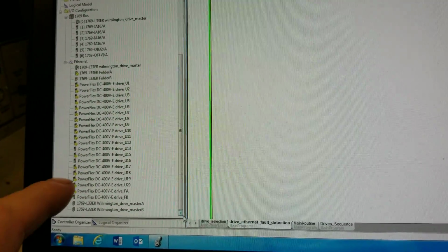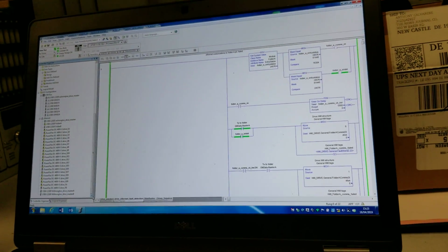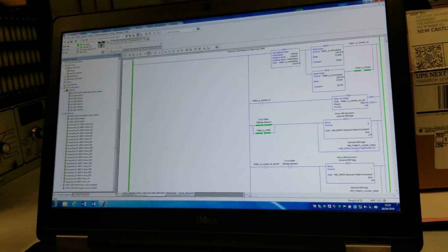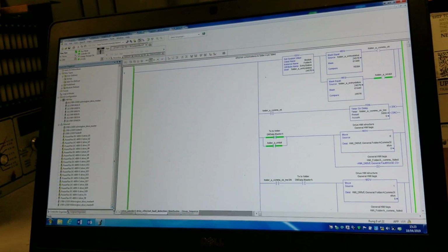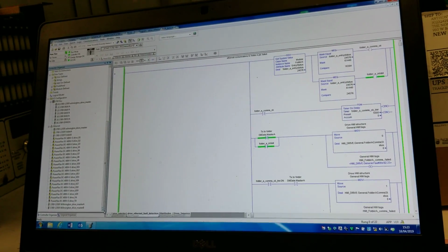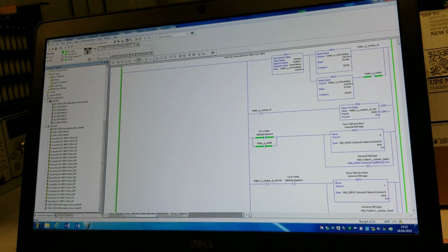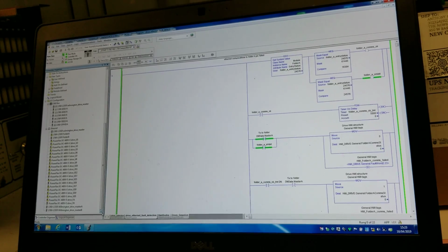So we've got the drive 13 on, no yellow thing. We've got the drive 16 on, and we've got the folder B drive on, and everything's happy. If one of the drives was not active and the comms was satisfactory, you would see something here. You can get triangles on here. The triangles indicate a fault. Shall we have a fault so you can see a triangle?